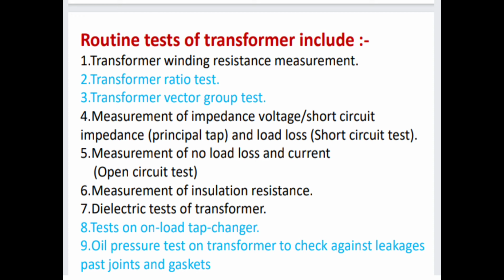So see, first is transformer winding resistance measurement, second is transformer ratio test, third is transformer vector group test. Fourth is measurement of impedance voltage, short circuit impedance and load loss. Fifth is measurement of no load loss and current. Sixth is measurement of insulation resistance. Seventh is dielectric test of transformer. Eighth is test on load tap changer. Ninth is oil pressure test on transformer to check against leakage past joints and gaskets.